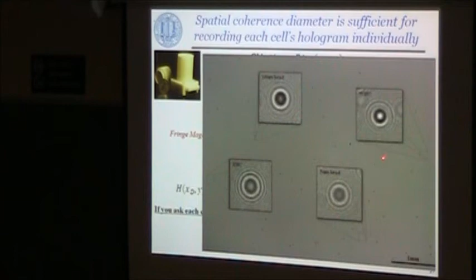We do not use lasers, so our bandwidths are on the order of 10 nanometers or so. That would not be enough if we were to use a large distance between the cell and the detector array, because some of these oblique rays would not have temporal coherence with respect to the background ray. But because we keep the distances very close to the surface of the active region of the CMOS detector array, we can live with even a 10 to 20 nanometer bandwidth of LED without killing our fringes. And that's a unique window which permits us to let information in through a temporal coherence gate and reject the unuseful information, which wouldn't be sampled anyway by the pixel size, which in this case is 2.2.